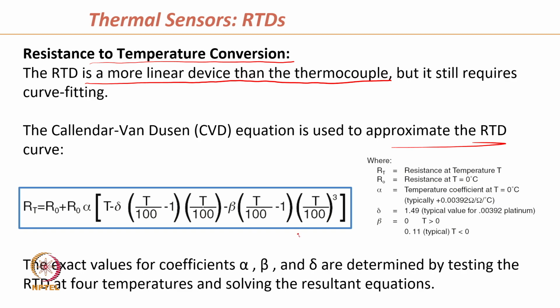So, this is the complete equation where we have RT, which is resistance at temperature T, R naught is the resistance at 0 degree C, which is a fixed value, alpha is the temperature coefficient for that particular metal, delta is typically 1.49 for platinum, and beta is typically 0 for T greater than 0, or it is 0.11 for T less than 0. The exact values of coefficients alpha, beta and delta are determined by testing the RTD at 4 different temperatures and solving the resulting equations.